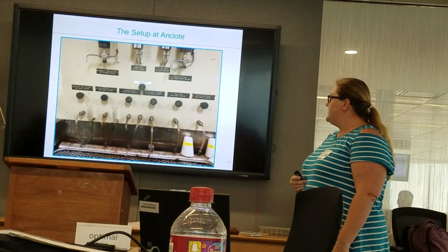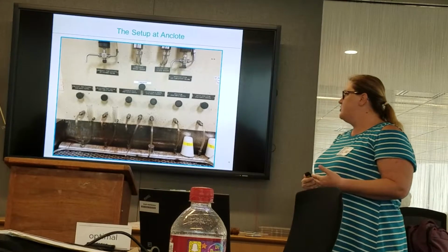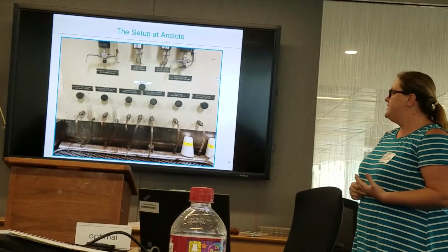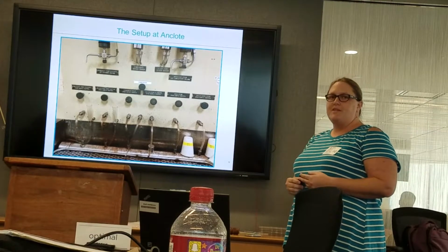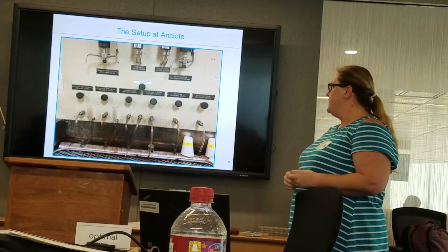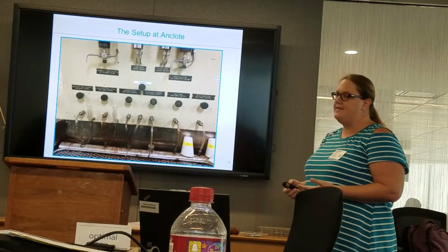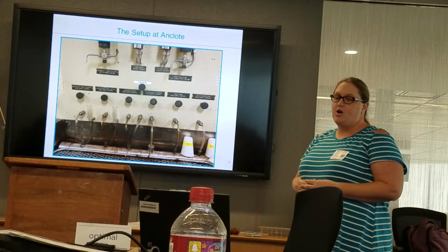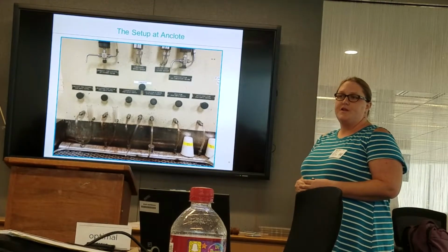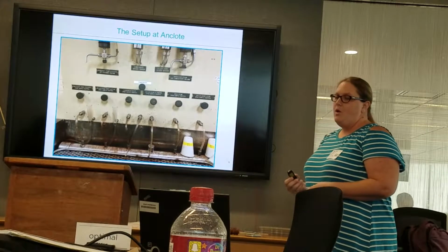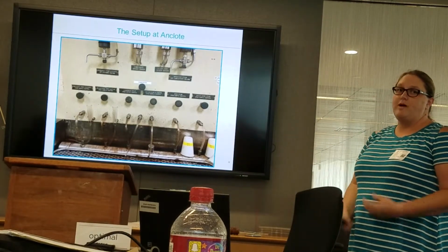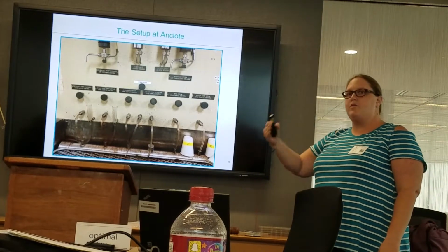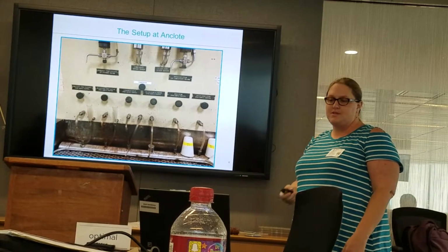So this is our current setup at Anclote. We have 6 grab samples. We have our condensate, our boiler feed, our economizer, boiler drum, main steam, and saturated steam sample lines. Currently, our non-degas cation conductivity columns and probes are on our condensate and our steam. But with this, the Mark 24, we could connect it to any sample line. So that really helped us in troubleshooting throughout our water cycle system.